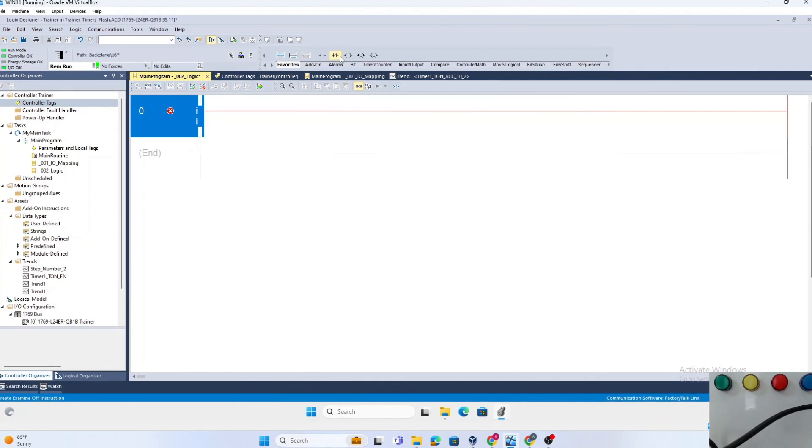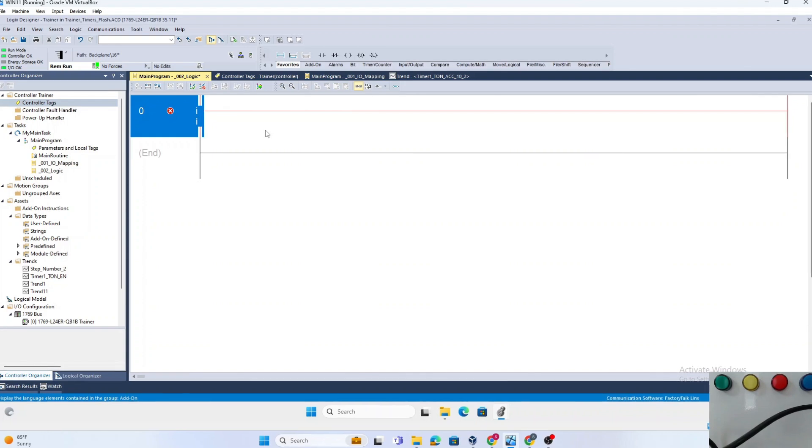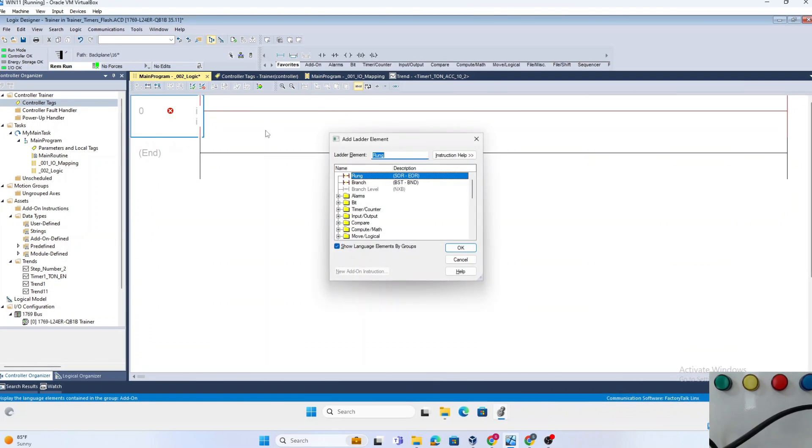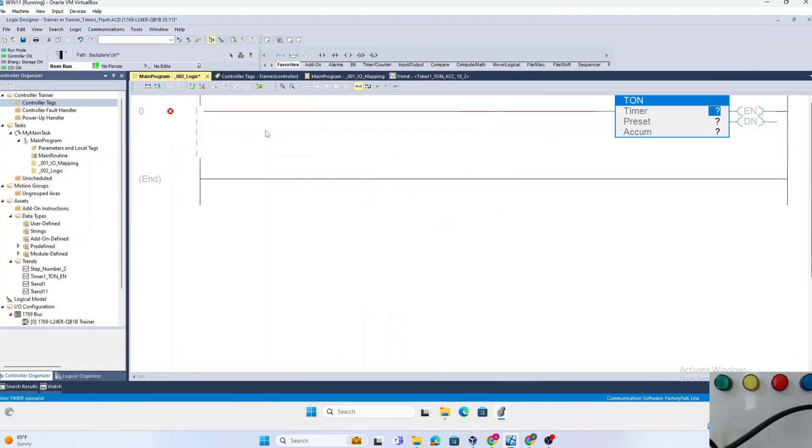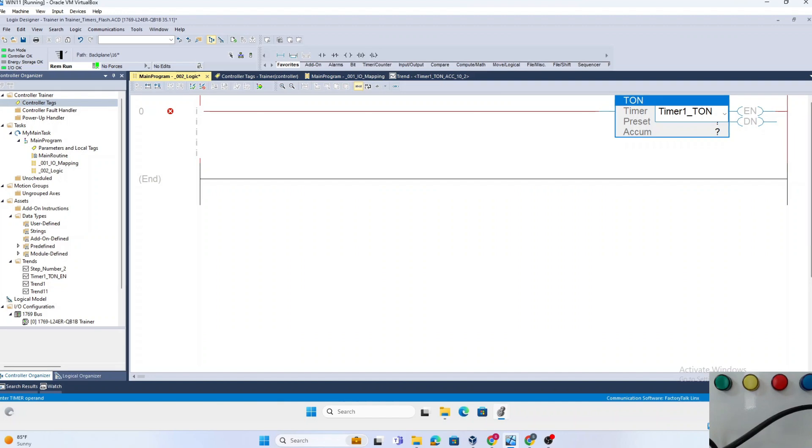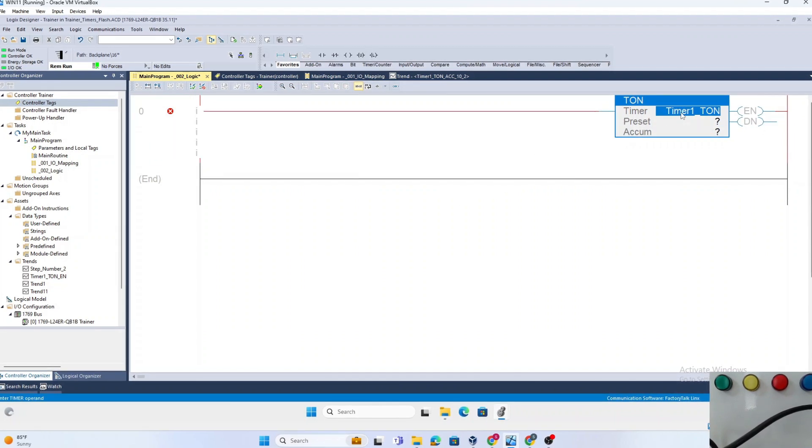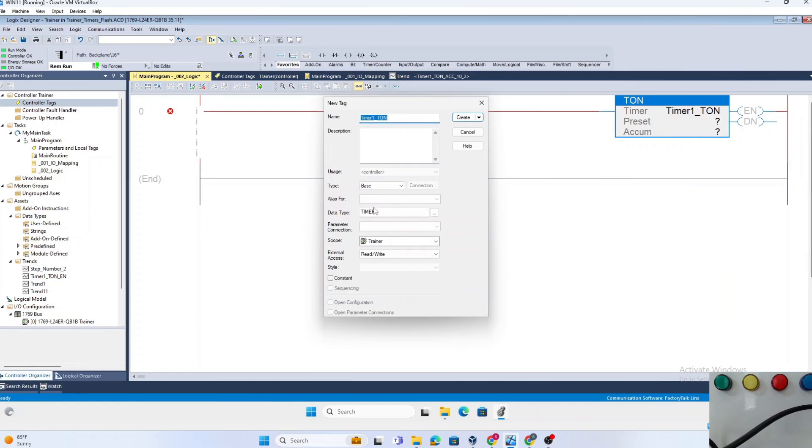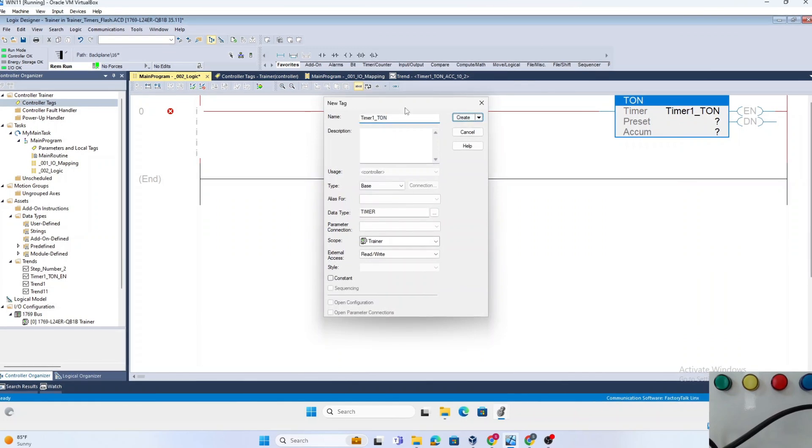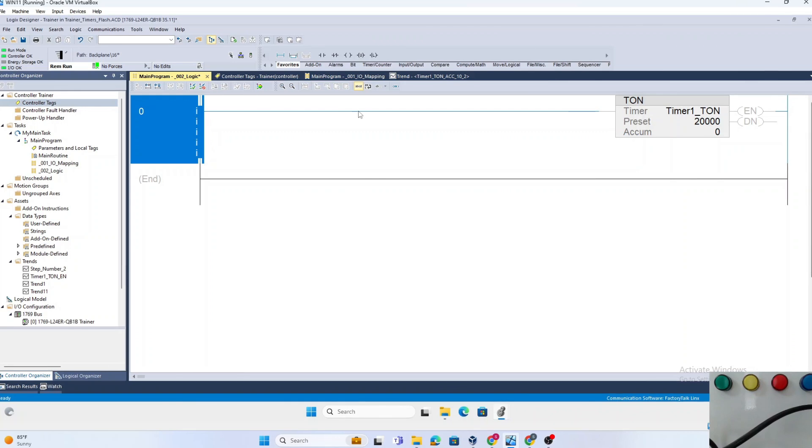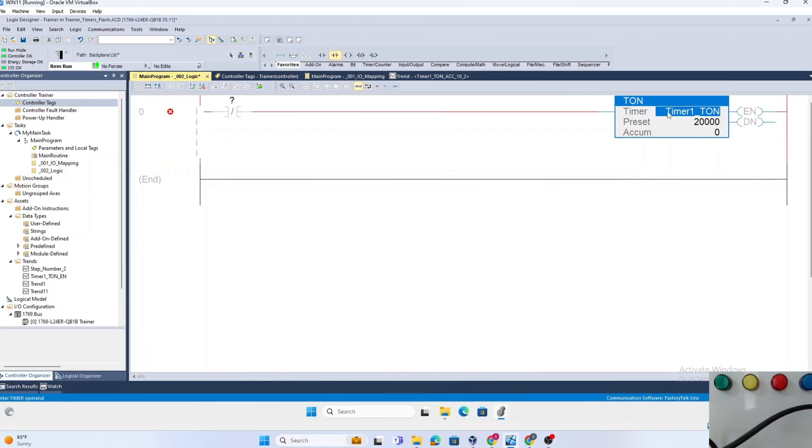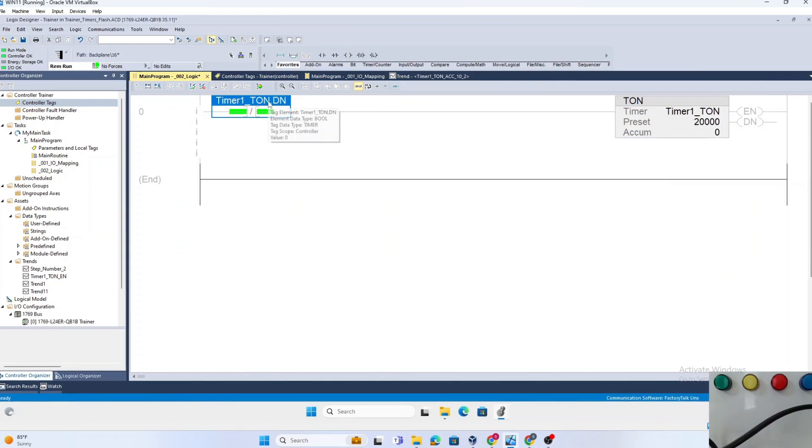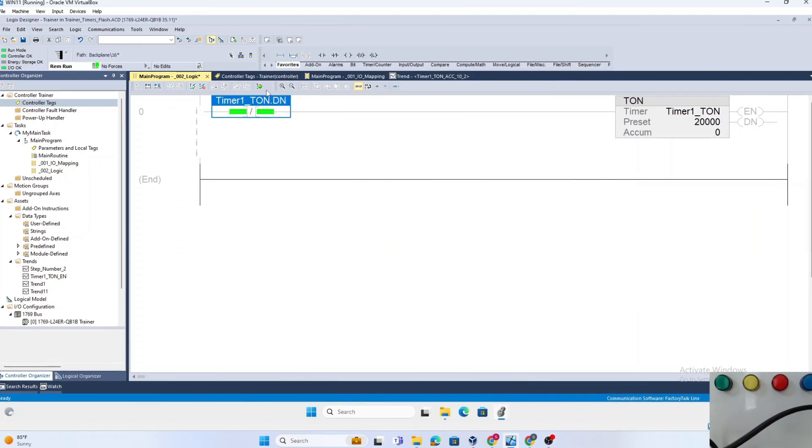So without delay, let's start writing the logic. To begin, we'll insert a TON instruction called Timer1. Let's create a new timer and set the preset to 20 seconds. We'll make this a self-starting timer by using the NOT of the done bit. Now we've created a self-starting timer which keeps timing for 20 seconds.